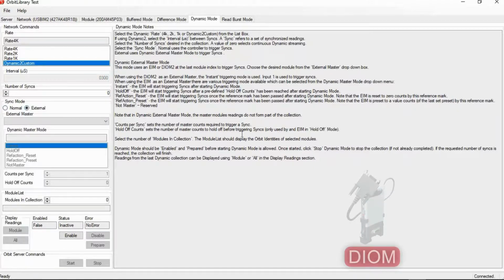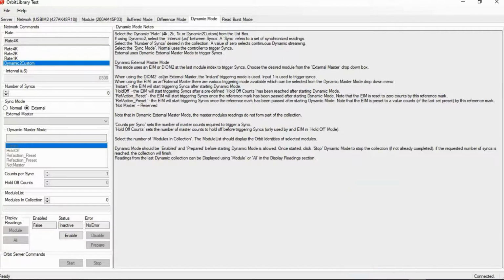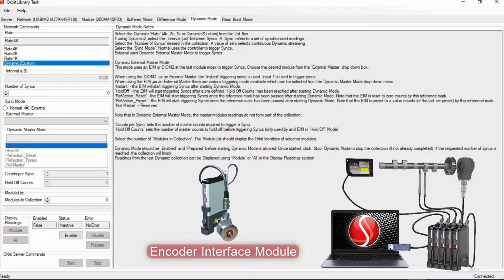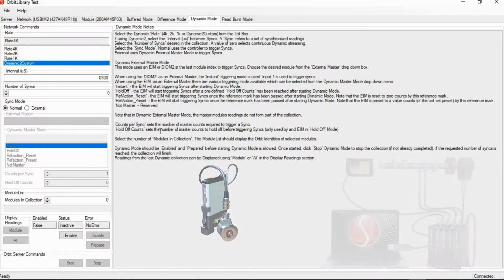But for external, this is where you can use a digital input-output module, or a DIOM2, where you can use an external switch to trigger the dynamic readings, or you can use the encoder interface module for applications like the picture that you see there. You can have a rotary encoder trigger the dynamic readings. So for example, on an application like that, where you want to have all the readings at 1 degree, all the readings at 2 degrees, all the readings at 3 degrees, as a shaft rotates for the probes, this is something where you can use a rotary encoder, an encoder interface module, and tie that into Orbit and have that trigger it. Right now we'll just do this with normal.